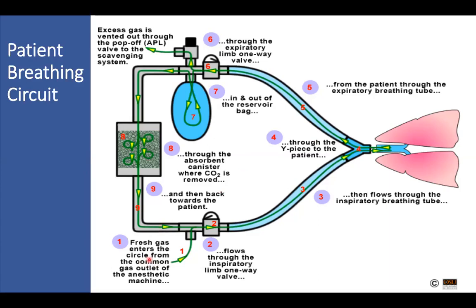So you've got fresh gas that enters what we call a circle loop, and it comes in to the circuit through a one-way valve, and it goes through the inspiratory limb through a one-way valve to the patient. And you'll have the Y piece that connects the inspiratory limb, the expiratory limb. And then usually right after the Y piece, you'll have a filter, a heat moisture exchange filter. And then you'll see the expiratory limb coming back out through a one-way valve to the vent.